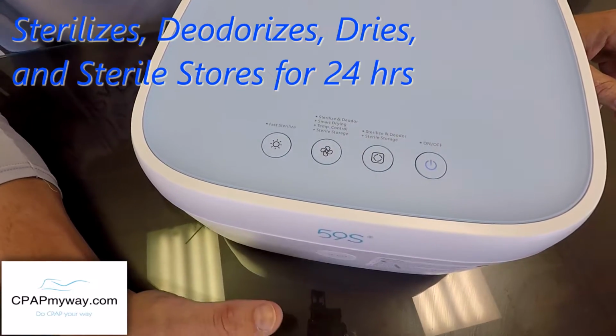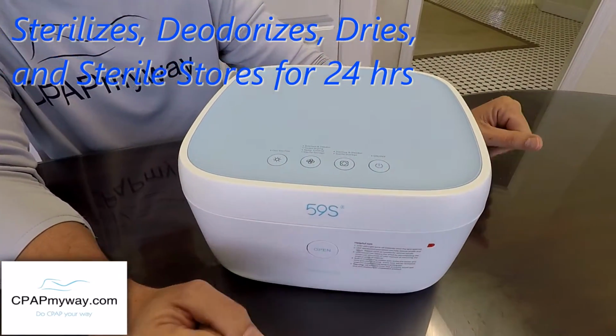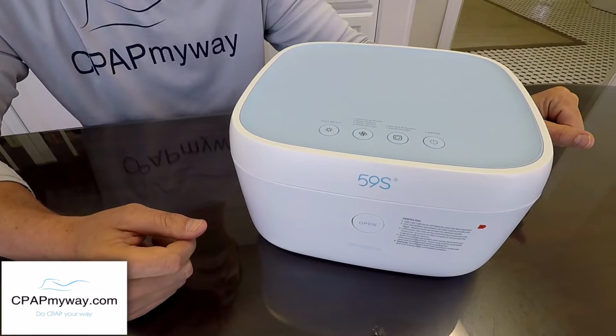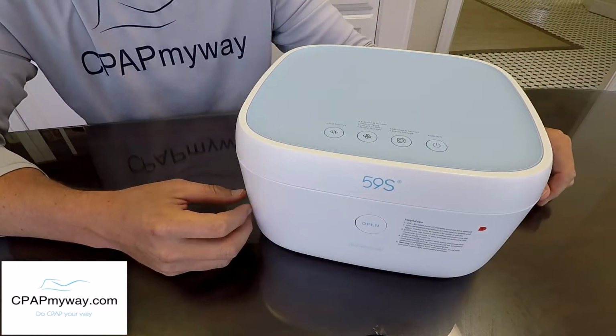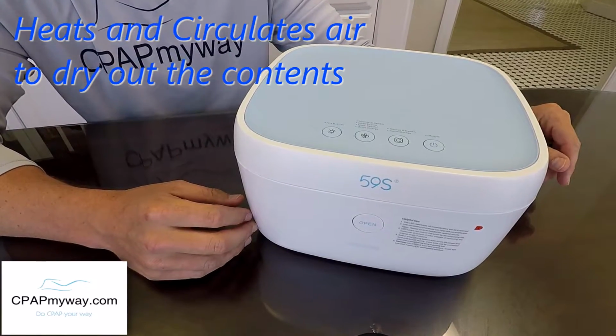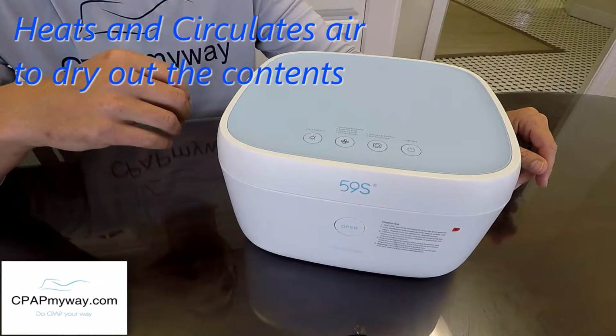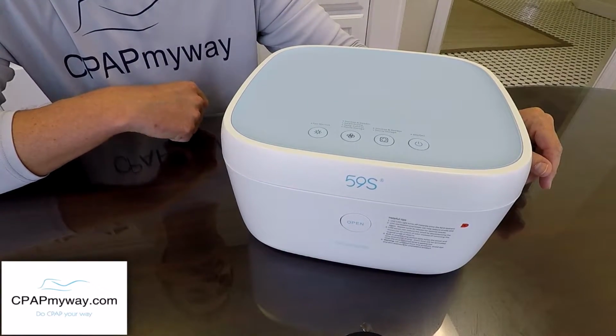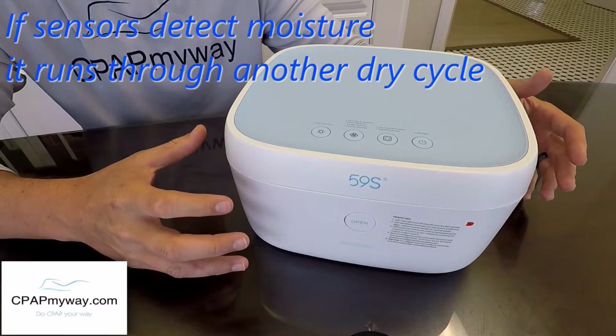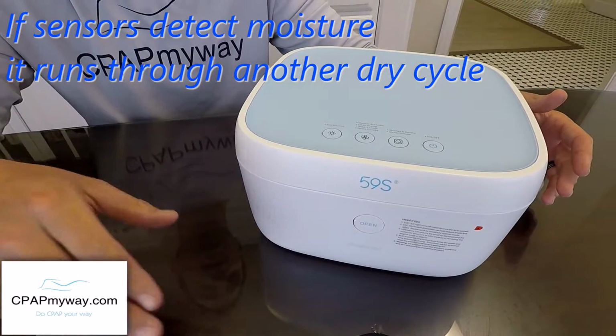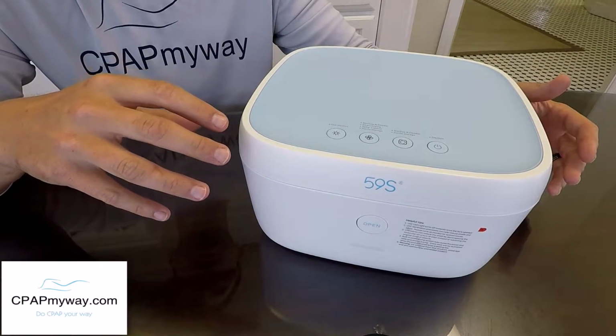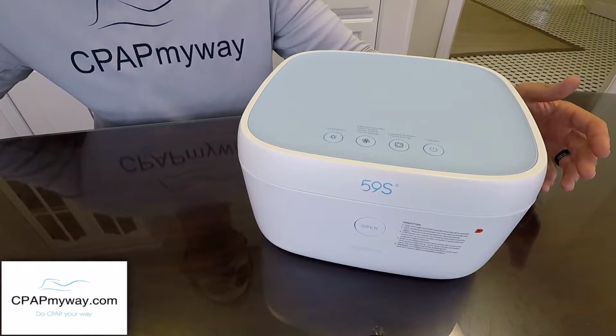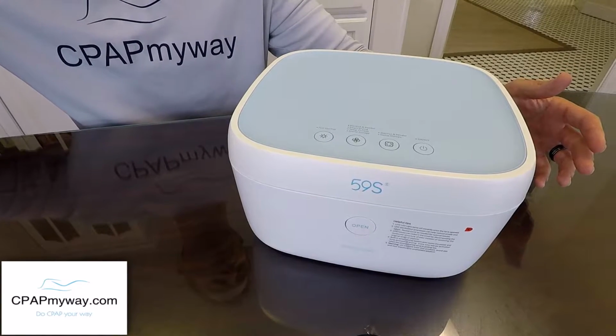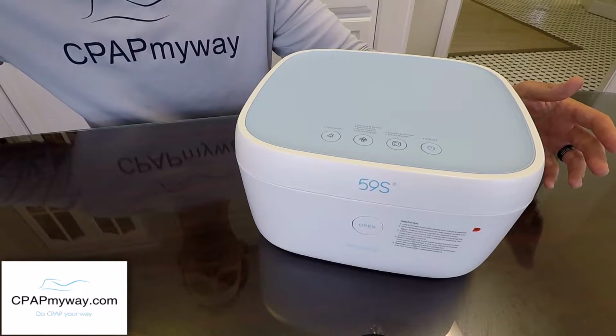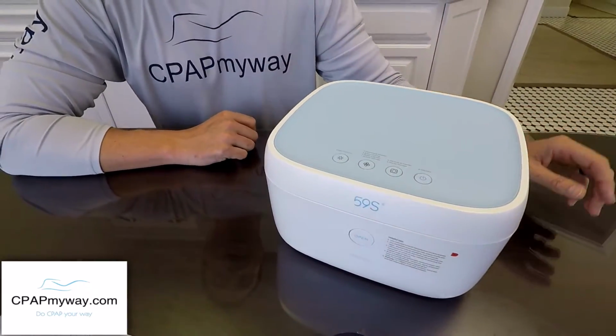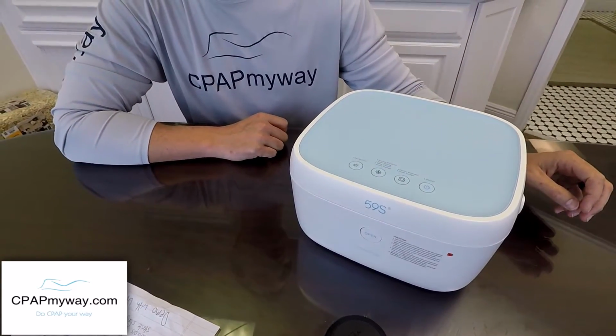That's a really cool deal because it'll run through the same sterilization and deodorization 180 seconds. And then it goes into a heated dry mode where it will heat up the internal air to about 90 degrees plus, and it dries everything out. It runs through about 60 minutes of drying, and it's got internal sensors that allow it to know if it's dried fully. If it hasn't, then it will run through another cycle. Once it's fully dried everything, it will go into a sterile storage mode as well, just so that it's keeping it nice and sterile until you're ready to use whatever's inside. So we'll go through a quick demo with you and show how it all works.